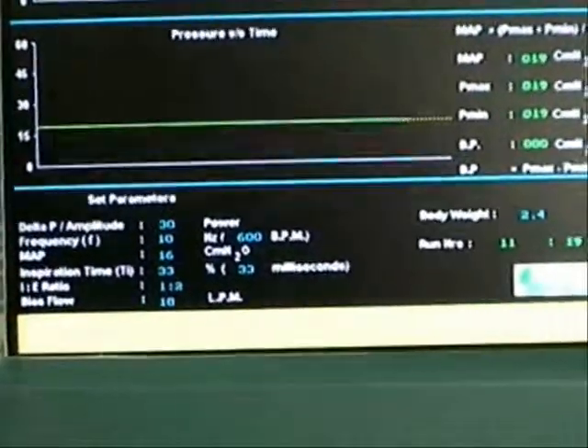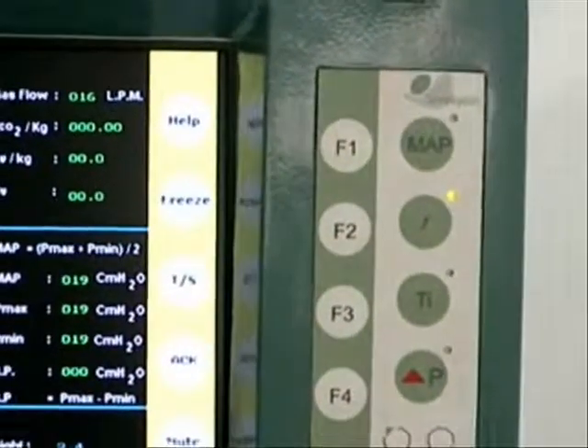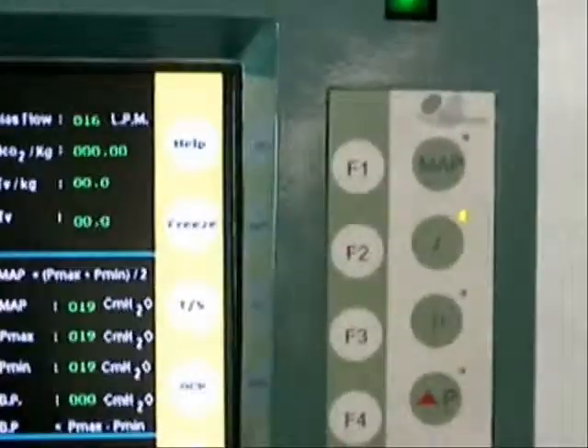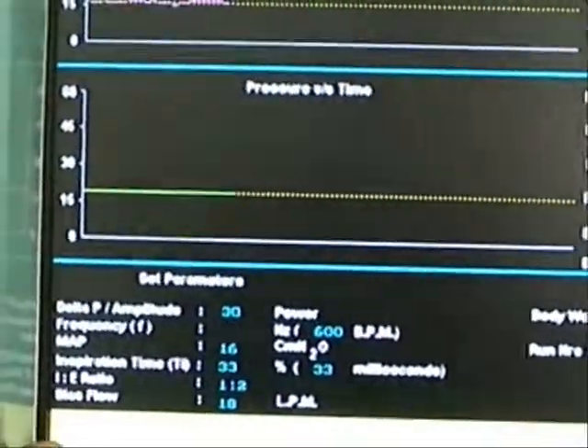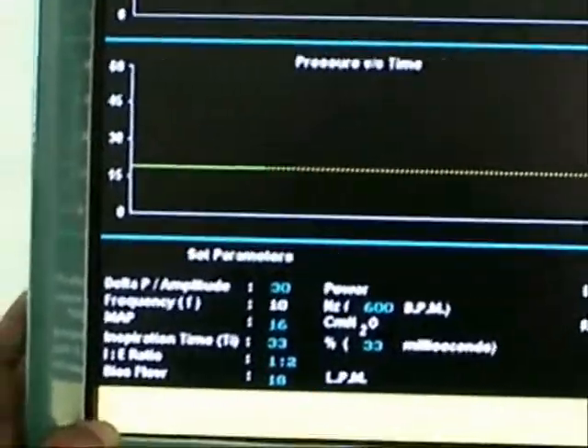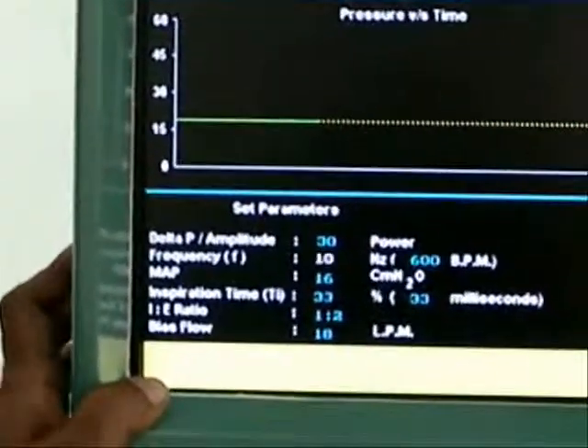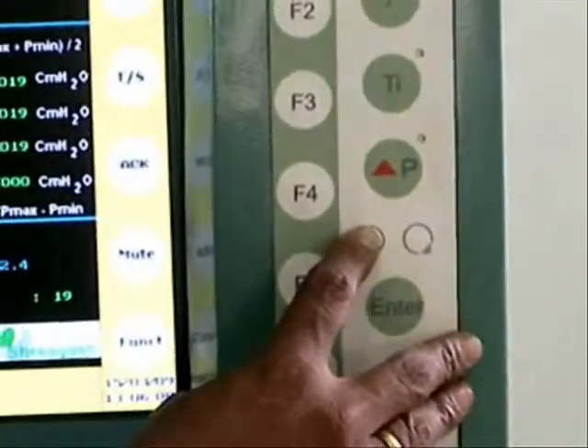Now once you enter it, this value is remembered and memorized by the computer inside. Now you have to set the frequency. Press the F key here. Again, an LED indication shows which parameter you are going to set. The set frequency here is 10. Now I have a newborn baby, a 600 gram or 700 gram baby, and I want to set a frequency of say 15 Hertz. So again I use these up and down keys. Set frequency 15, press enter.